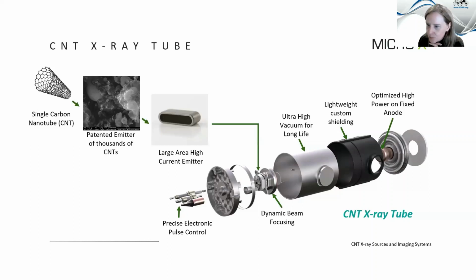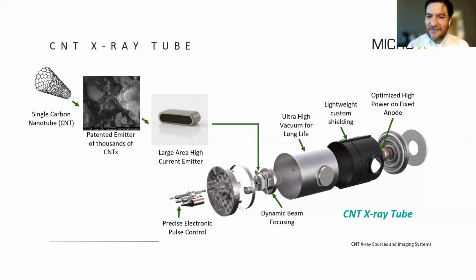What is the leakage outside the X-ray tube? I presume it's all made to standards. Yes, it's all made to standard. We use a metal ceramic tube, so you get some attenuation just because of the stainless steel housing, and then we encapsulate that in additional shielding. You can actually see it there. It's a tungsten filled polymer that allows us to make a molded shielding that's smaller and lighter. It's smaller and lighter not because it's less dense, but because it can be molded to the exact shape and optimized. So we meet standards in every one of our mobile imaging systems.